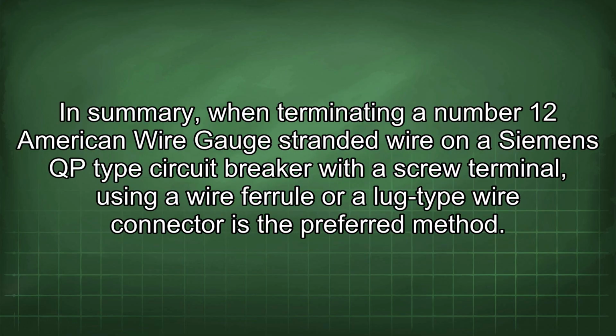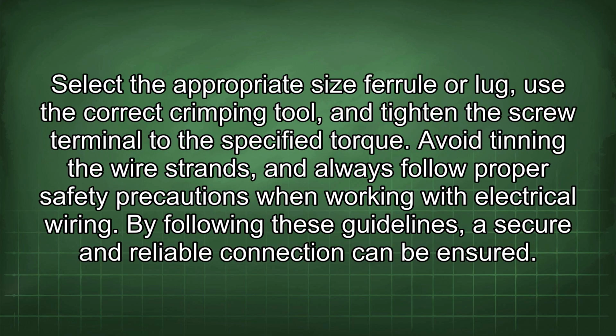In summary, when terminating a number 12 American wire gauge stranded wire on a Siemens QP-type circuit breaker with a screw terminal, using a wire ferrule or a lug-type wire connector is the preferred method. Select the appropriate size ferrule or lug. Use the correct crimping tool and tighten the screw terminal to the specified torque. Avoid tinning the wire strands and always follow proper safety precautions when working with electrical wiring. By following these guidelines, a secure and reliable connection can be ensured.